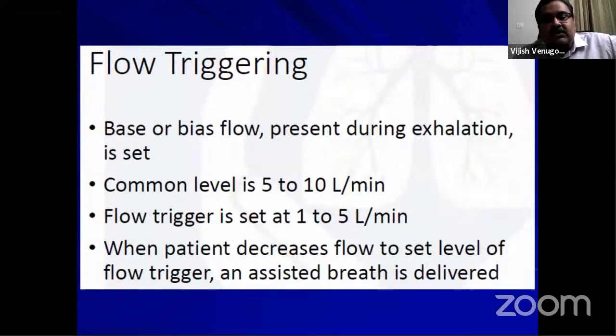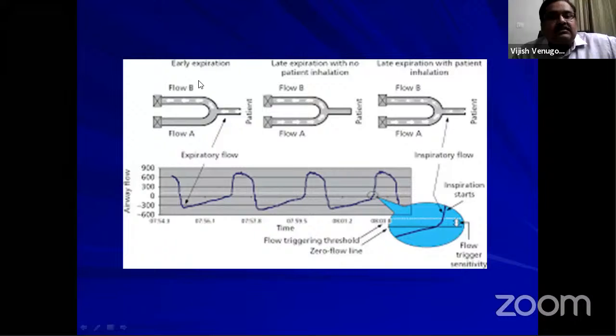Now coming to flow triggering, it is very important to know that there is something called a base or bias flow present in the circuit immediately after exhalation. This is usually around 5 to 8 liters per minute. And the flow trigger we set is usually 1 to 5 liters, or commonly 2 liters per minute. So when a patient decreases flow to the set level of flow trigger, an assisted breath is delivered. So that is flow triggering. If you look at this picture here, the flow B and flow A. Now here the patient is exhaling. If you can see my arrow, the patient is exhaling there. And at the end of exhalation, there is a base flow within the ventilator. And now this patient will take a breath. He will now inspire.